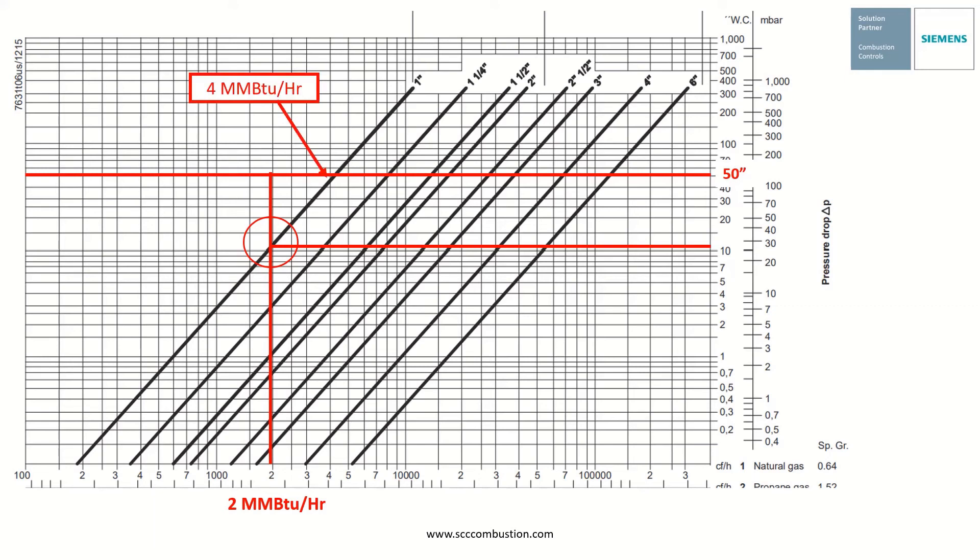For reference, under these same pressure conditions, a 1 inch double valve can flow up to 4 million BTU per hour. A typical 4 million BTU per hour gas train would use a 2 inch double valve. And now with the SKP25, we would use a 1 inch double valve. So you can see the difference.